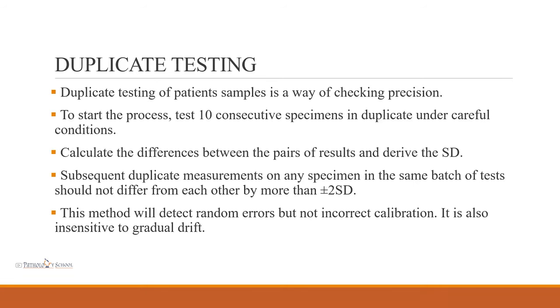Internal quality control also includes duplicate testing, which is a way of checking precision of the system. Ten consecutive specimens are run in duplicate under careful conditions. We calculate the differences between the pair of results, derive the standard deviation, and subsequent duplicate measurements on any specimen of the same batch should not differ by more than plus or minus 2 SD. This method is useful to detect random errors but will not detect systematic error or incorrect calibration, and is insensitive to gradual drift.